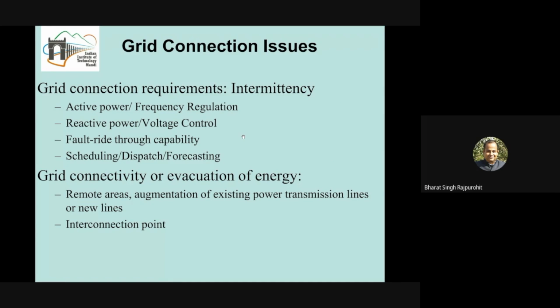Broadly, the grid codes are divided into three categories. One is known as active power control to maintain frequency regulation. Second one is reactive power control for voltage control. And third one is fault ride through capability.